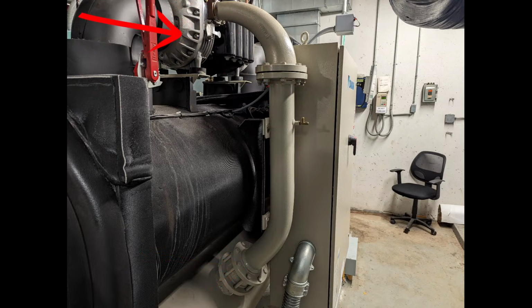So part of the point here is, as the centrifugal is spinning up, this check valve is there to help prevent a major backrush whenever we go to shut down. If memory serves, that's why they implemented it, to prevent the condenser pressure at coast down and shutdown from causing a major backrush into the compressor, which causes issues. This compressor also needs a second because it spins up very slowly, so the check valve helps it generate some lift, if you will, for the startup cycle until it gets up to speed. Once it's there, it's fine, and the check valve can open. Everything runs just fine from there.